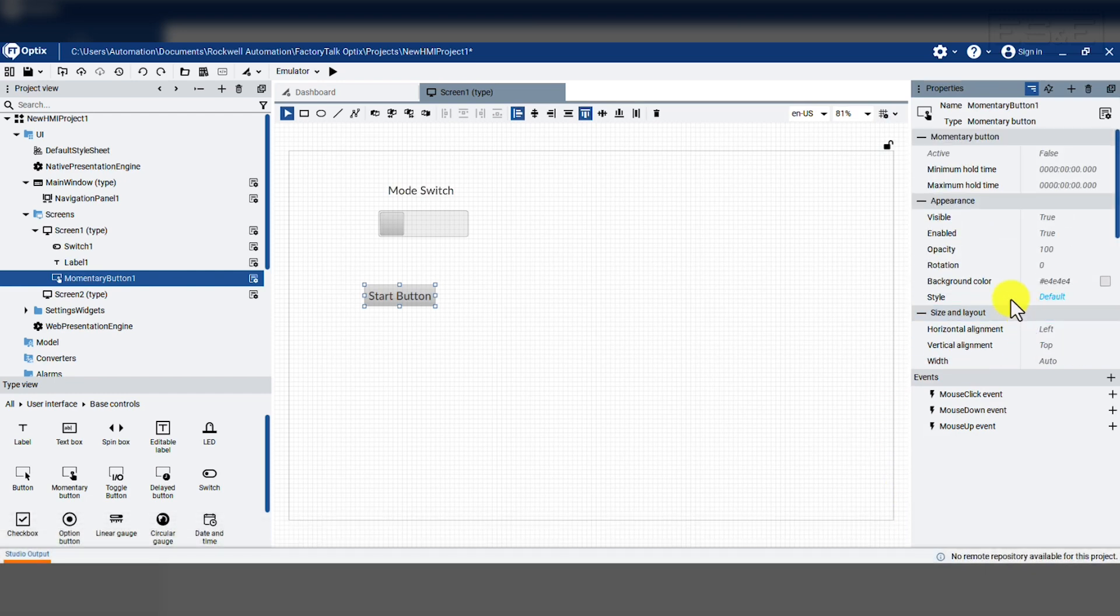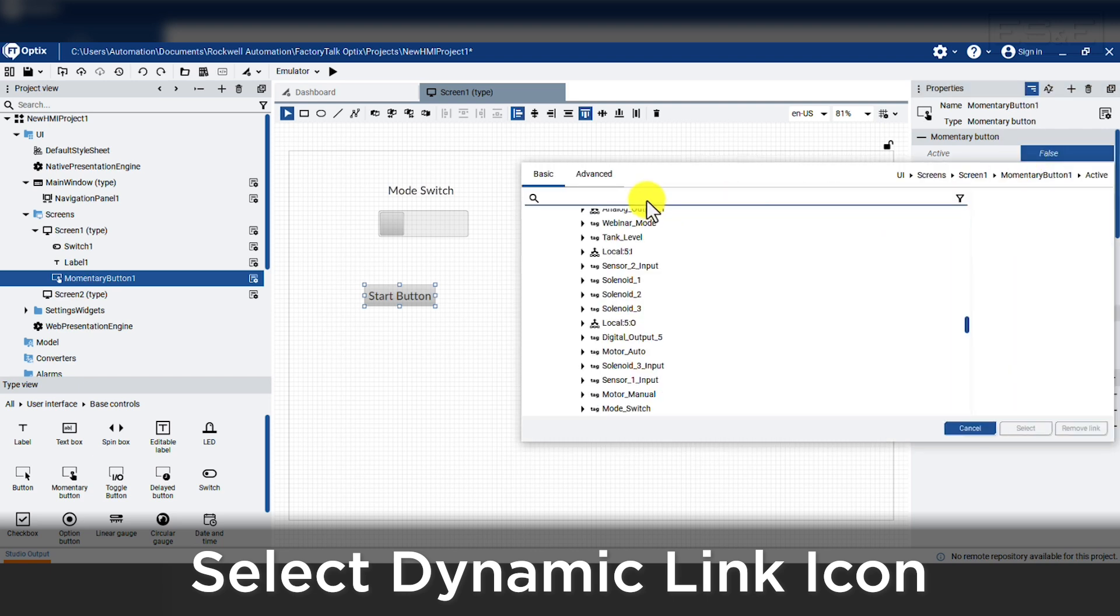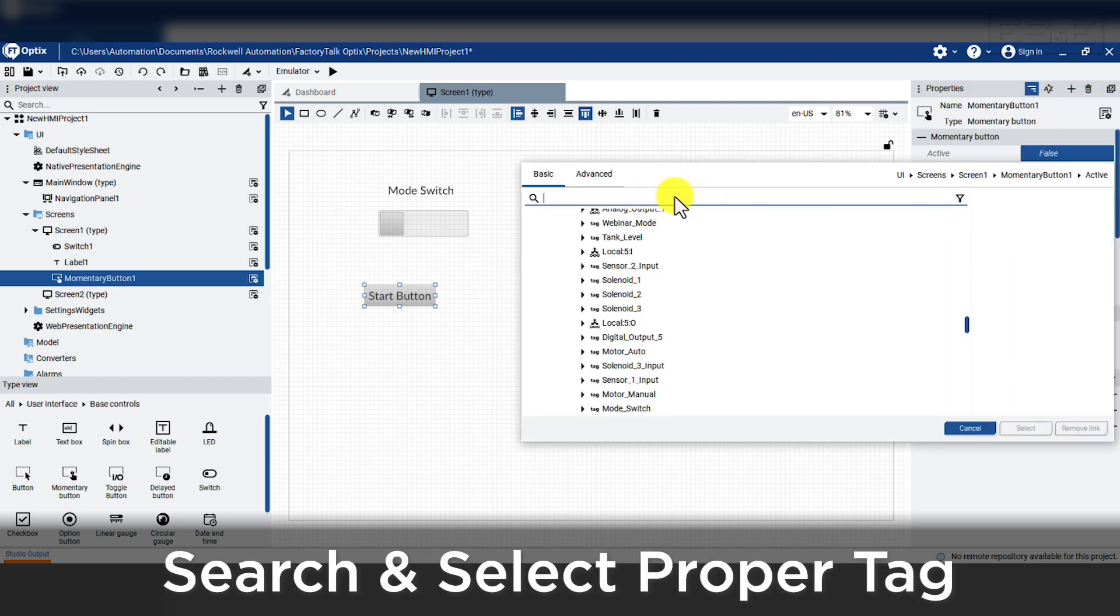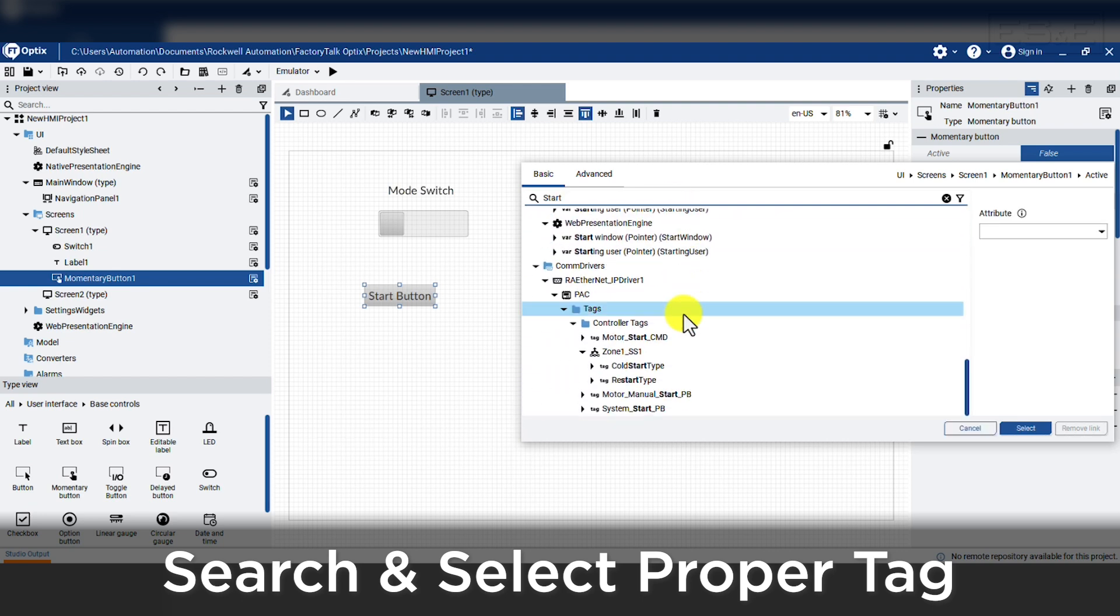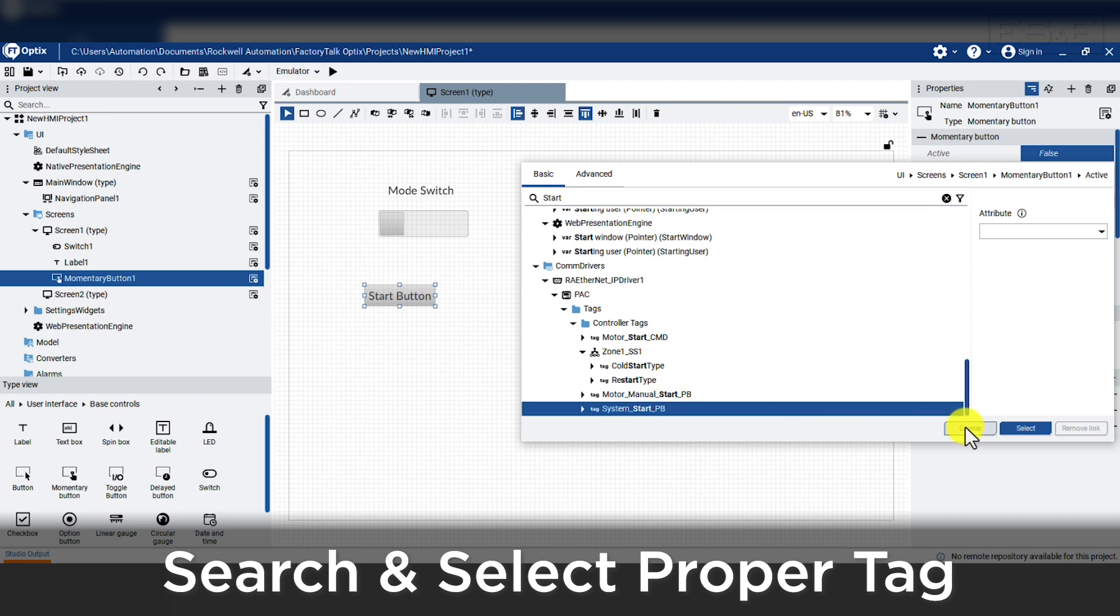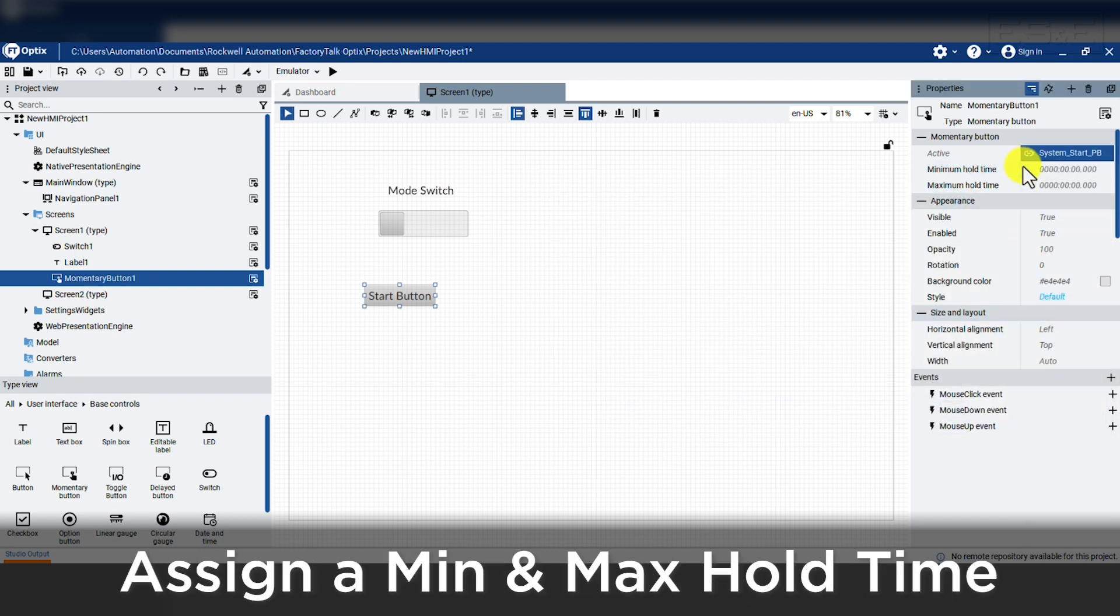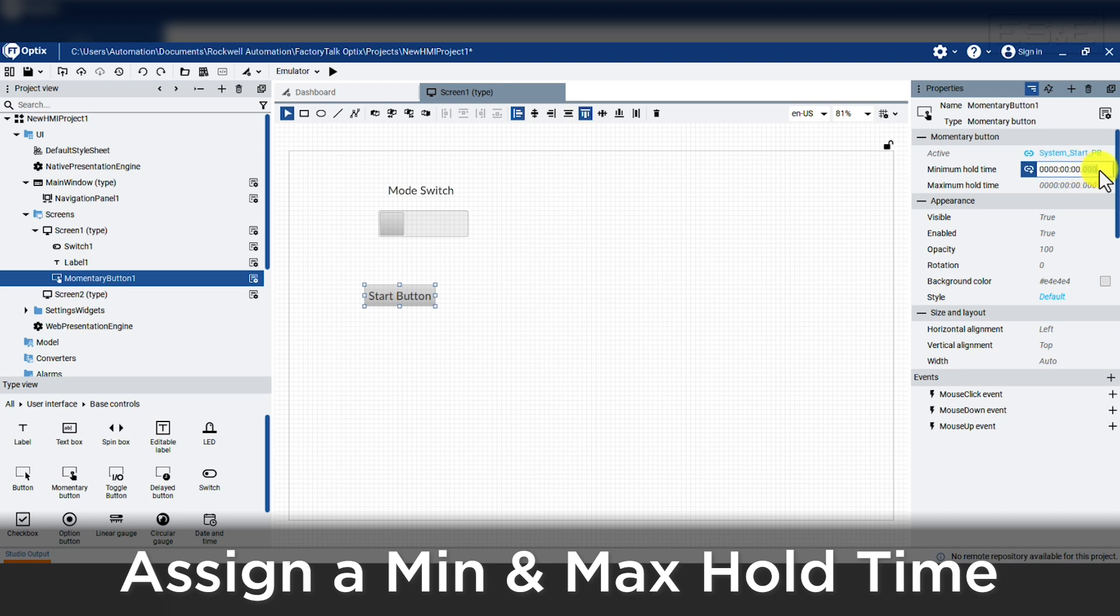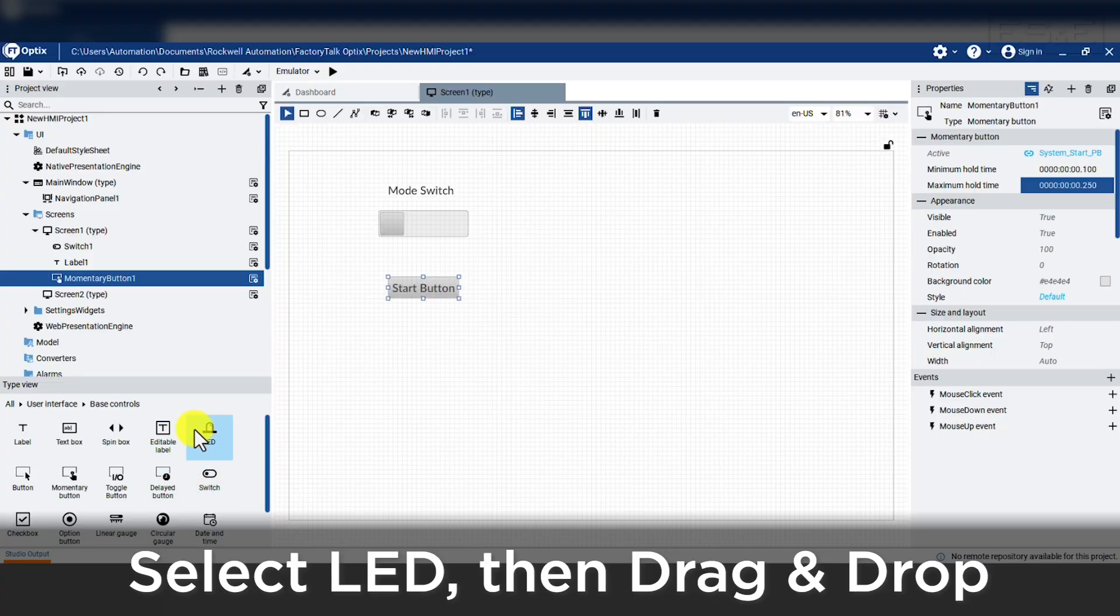Next, we need to assign an event for the button to do something. So we will select the dynamic link icon next to the active property. This pulls up all the tagable references and we will type in the word start. We will scroll down and find the tag called system start push button and once it is highlighted, we will press select. Let's assign min and max time for the button press. To do this, we will scroll up and add time to the min hold time and set it to 100 milliseconds. Also, adding a max hold time of 250 milliseconds. This will make a momentary push button, but it will also prevent someone from holding it down or accidentally pressing it. Now when we press the button down, it will be true and it will go back to false after 150 milliseconds.